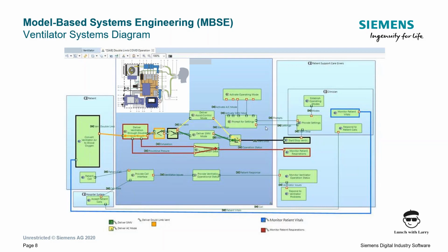So all of these component characteristics will have to be taken into account in the system simulation model to assess the performance of the ventilator. There's an even more critical component, that I would put in quotation marks here, to consider in our system model, and that is, of course, the patient. So the system model must also simulate the breathing behavior of the patient, and therefore must include data such as lung volume and lung stiffness.